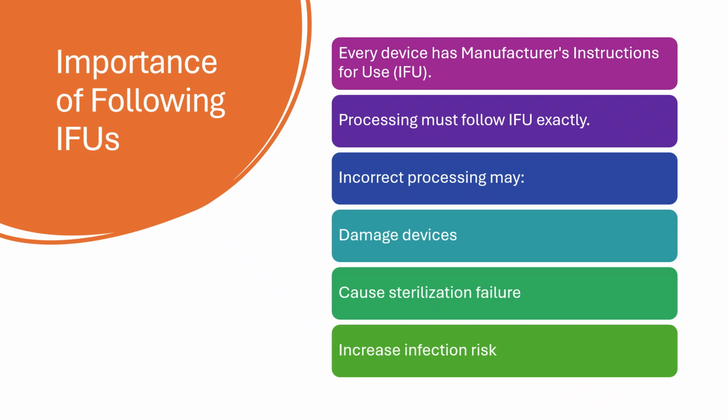Every reusable medical device comes with a manufacturer's instructions for use, commonly known as the IFU. These instructions specify cleaning methods, chemicals, sterilization parameters, and handling requirements. Failure to follow the IFU can result in ineffective sterilization, equipment damage, and increased infection risk.